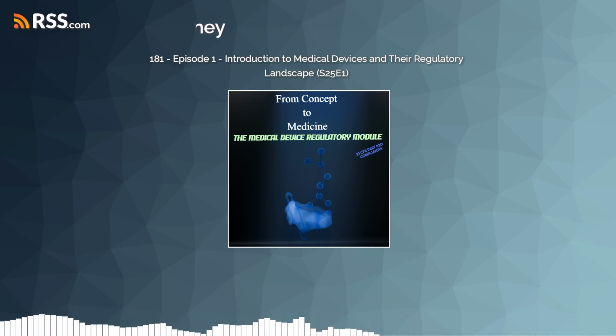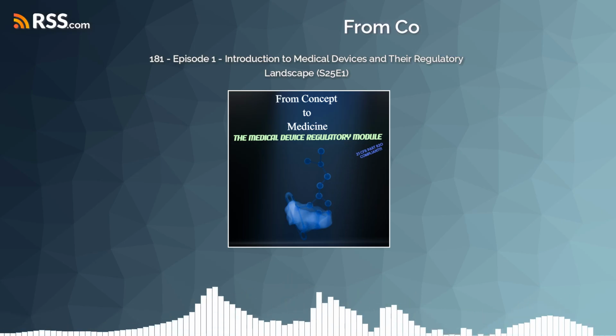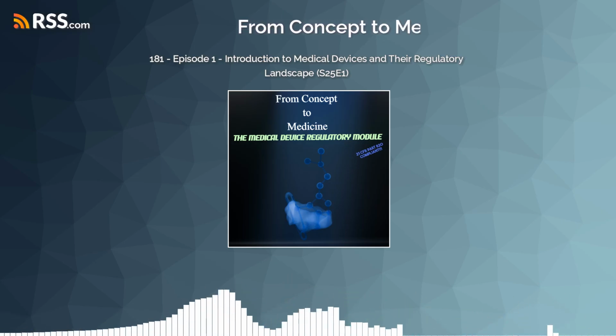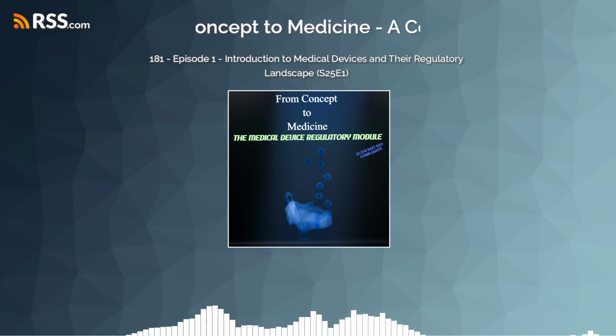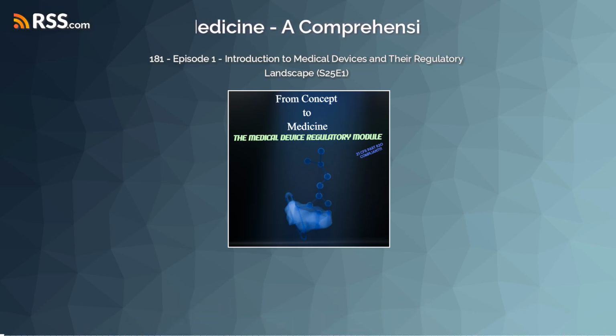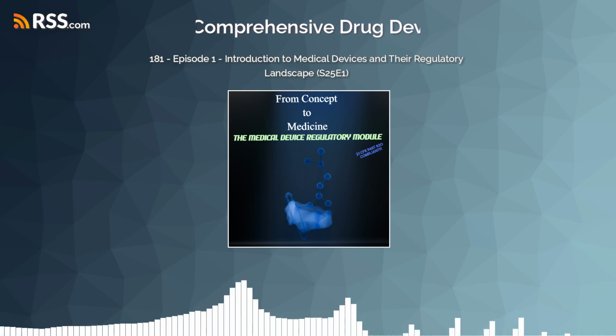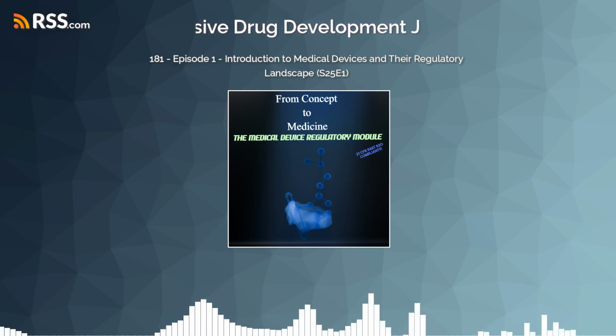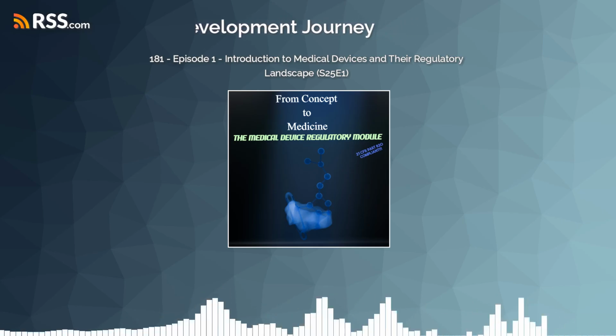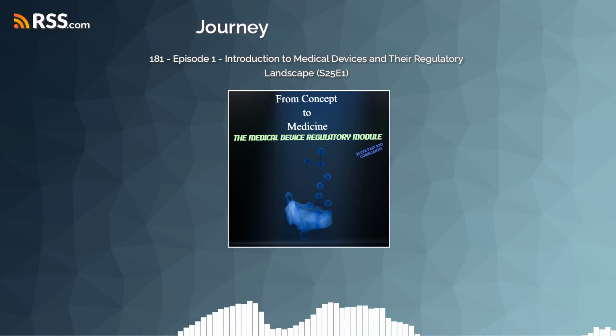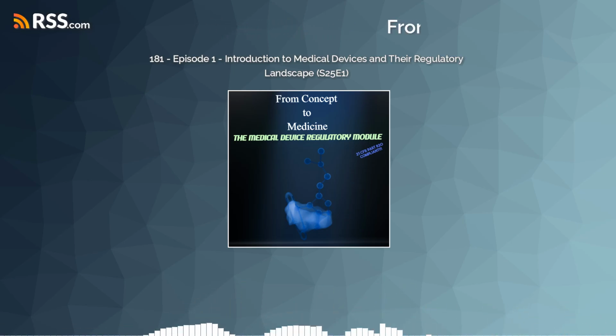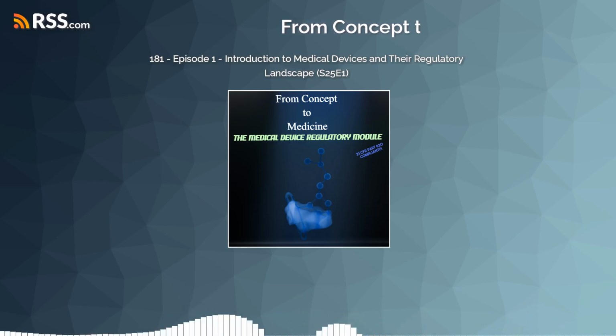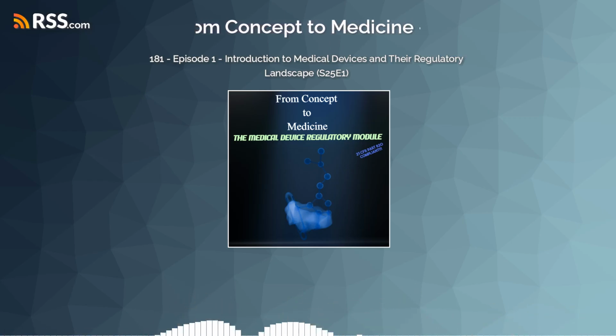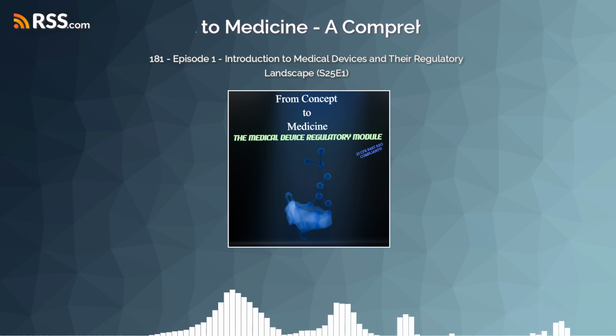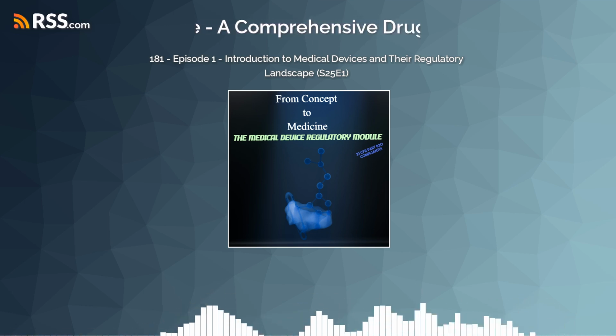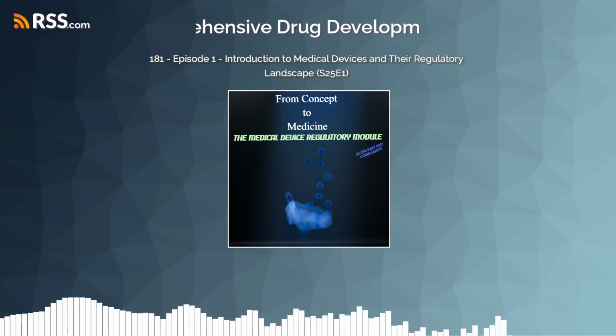And if a serious issue is found, a recall. If a manufacturer initiates a correction or a removal action to reduce a health risk posed by a device or to remedy a violation of the Act, they generally have to submit a written report to the FDA under 21 CFR Part 806. Recalls themselves are classified by the FDA based on the severity of the potential health risk, Class I being the most serious, involving potential death or serious injury. That classification then guides the urgency and scope of the recall communication strategy. Class I recall, most serious.